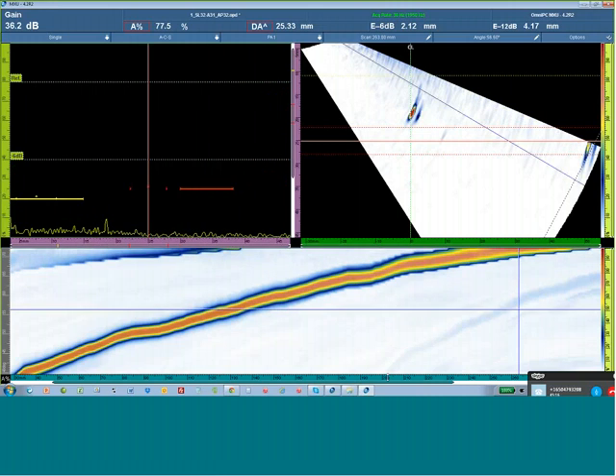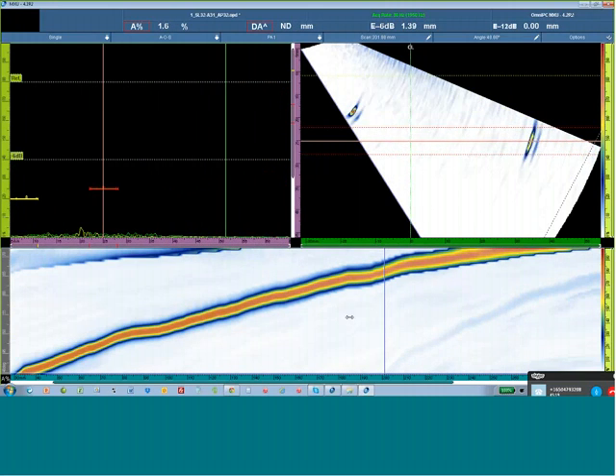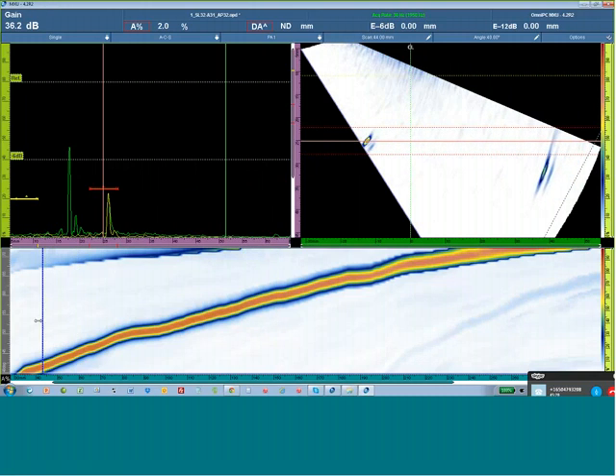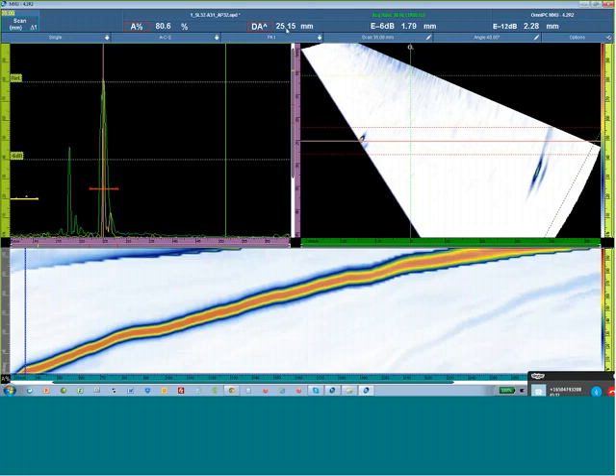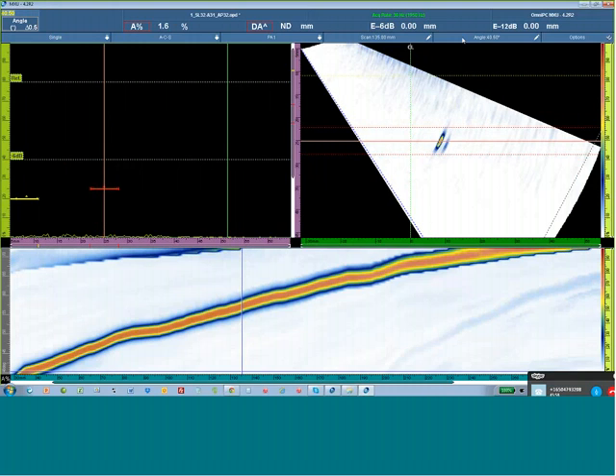So our very first indication is the ability to maintain correct angle, trigonometry, and beam shape on both sides of the sector scan. Correct depth. Again, we're already calibrated for amplitude. And in addition to the trigonometry, we're also looking at the size and the shape of the side drilled hole. Is it elongated? Is it symmetrical with the beam envelope? Is the energy in the center at the correct position?